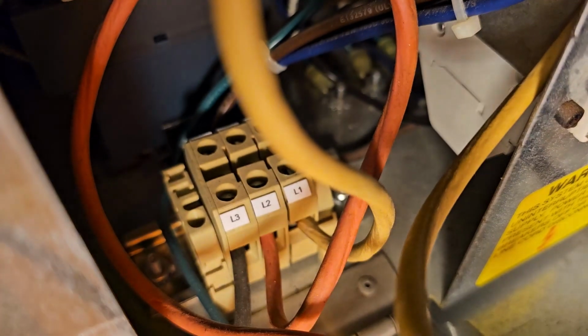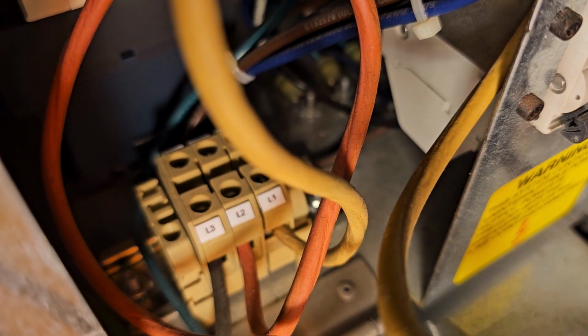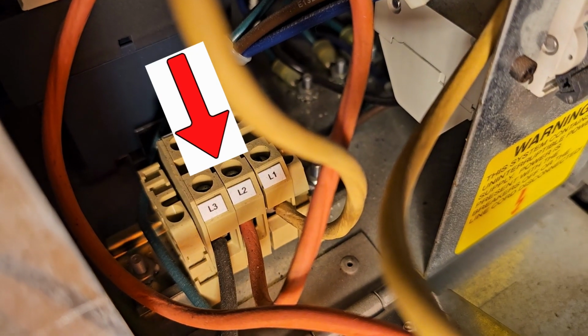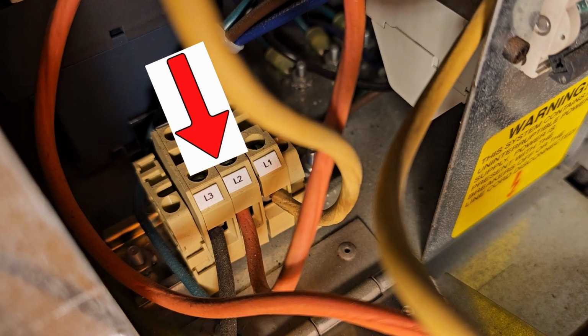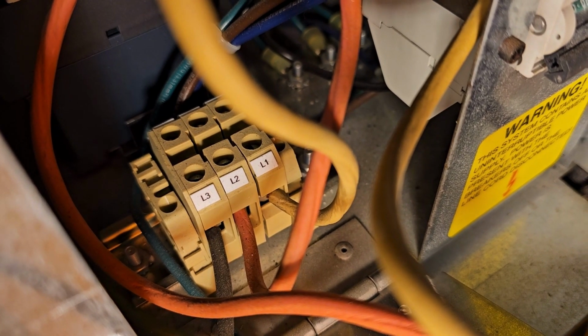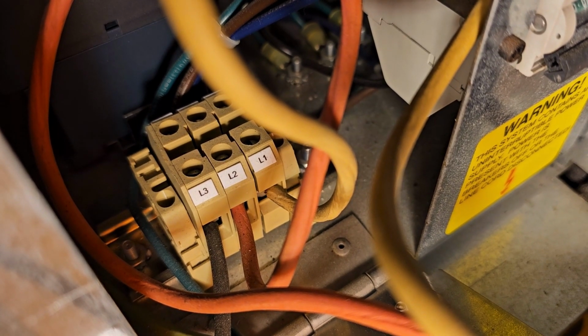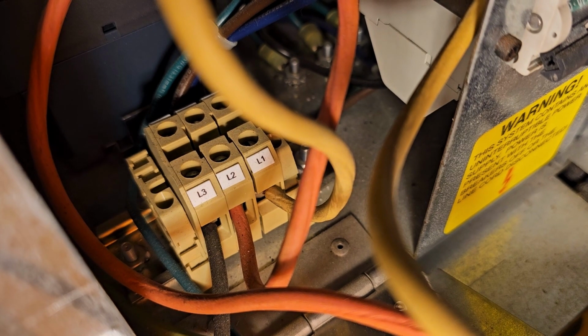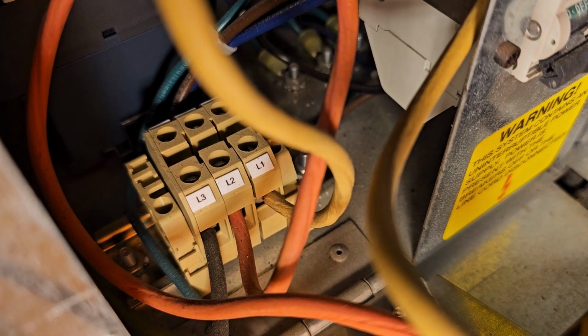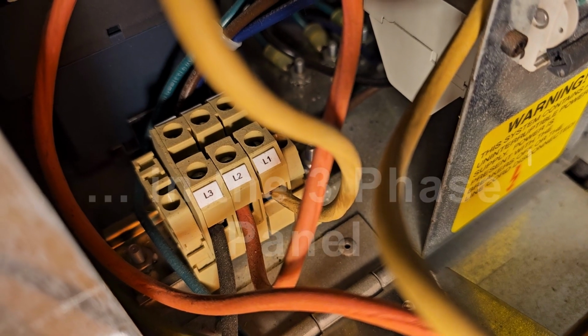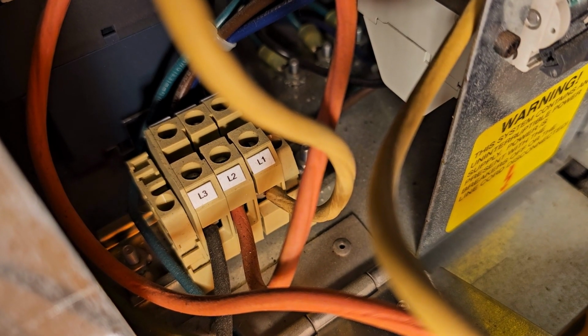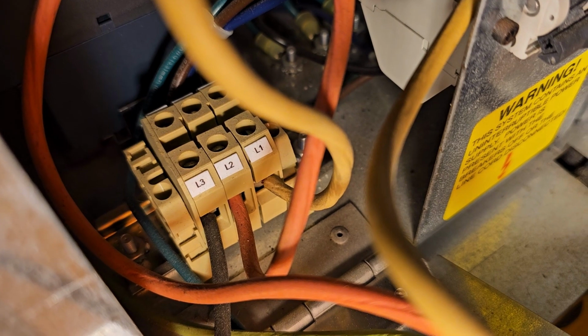Now, I don't know if you can see, it doesn't want to focus. Let me see if I can - there we go. You see those little labels on the wires, L1, L2, L3? Now, you see the black wire on the left is connected to L3, and the white wire on the right is connected to L1. In the sub panel, the black is on L1 and the white is on L3. So those two wires are reversed. The red on L2 is fine.